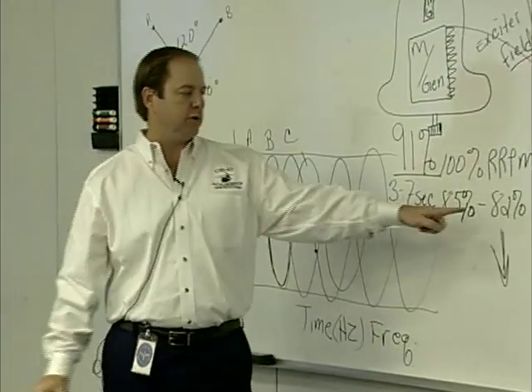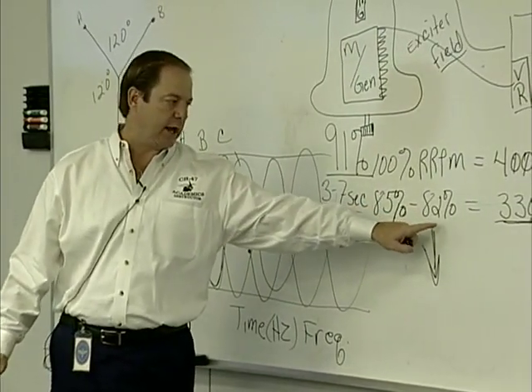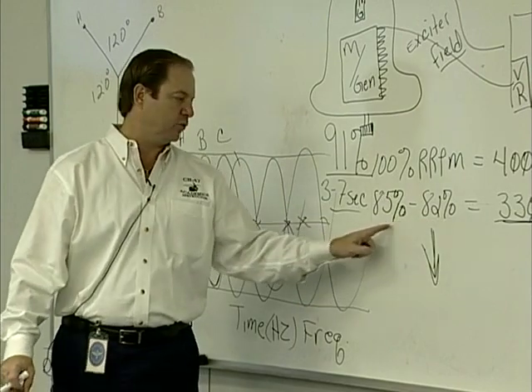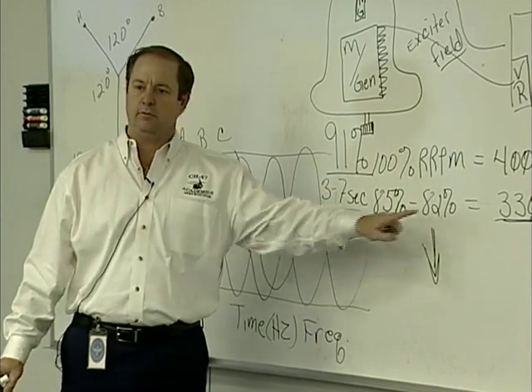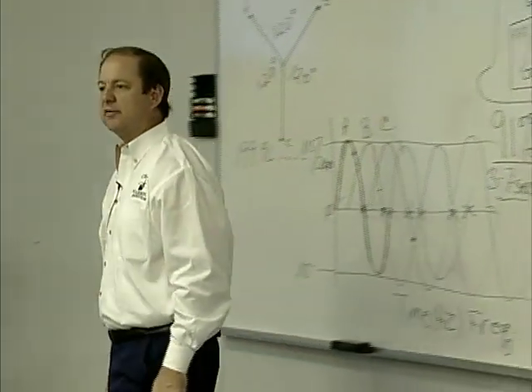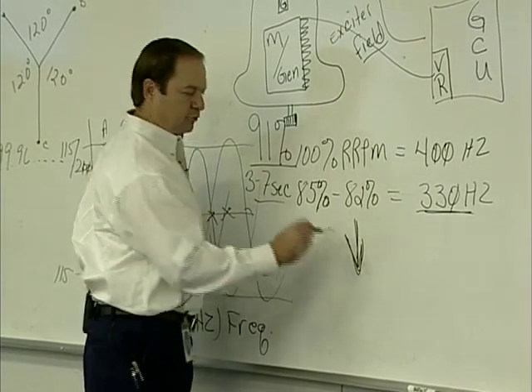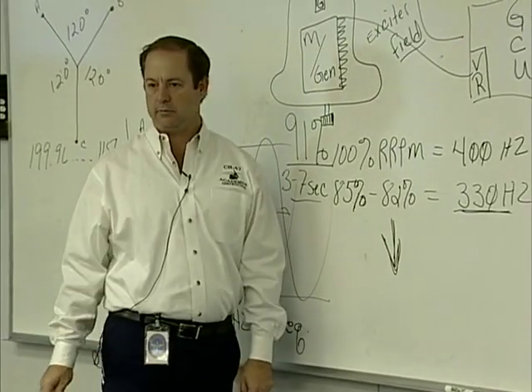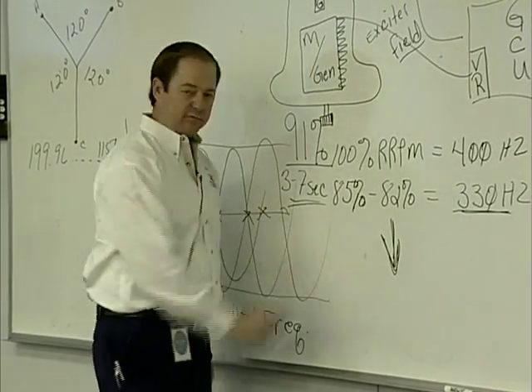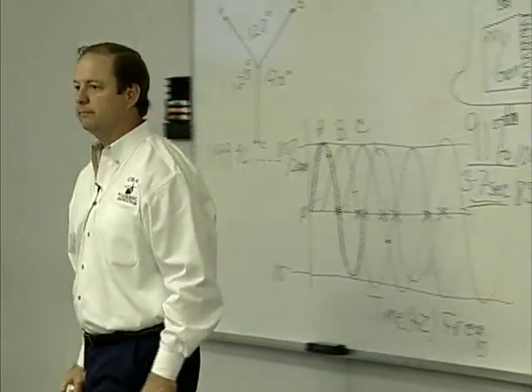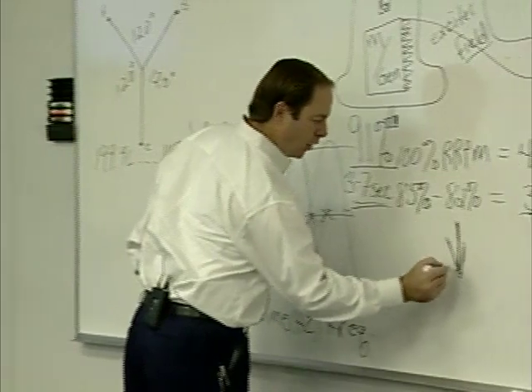What's the difference between what's happening here versus what's happening right here? What's going to be the difference? The difference is if you go below there, those generators are going to fail immediately. It does away with the 3 to 7 seconds. Does everybody understand that? Okay, where's it going to recover? Or what does it require me to do to recover it if I go below 82%?